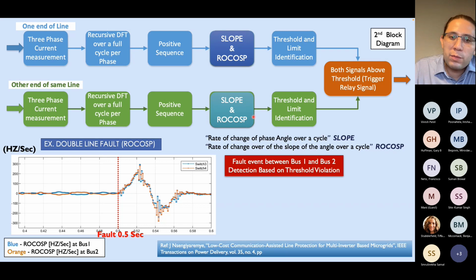The ROCOSP is the rate of change of the slope of the angle over a cycle. Here we utilize three cycles of measurement, which shows the robustness of the response. For the slope case, we utilize only 2 cycles. It's still robust, but we wanted to go a bit farther to be able to handle critical loads.